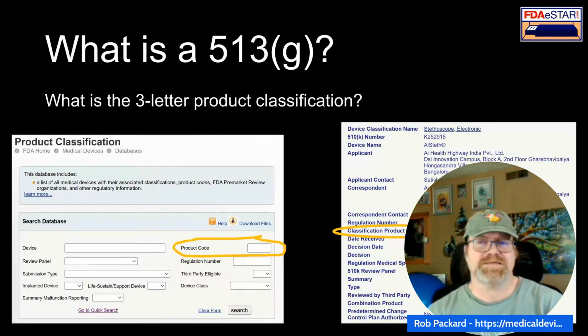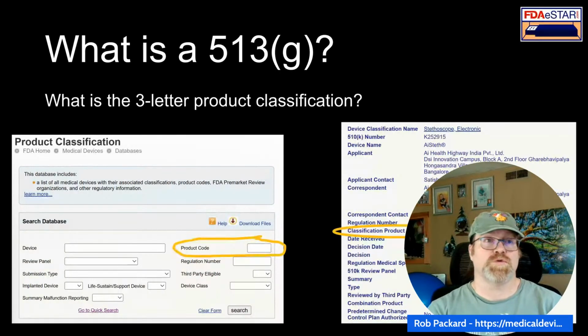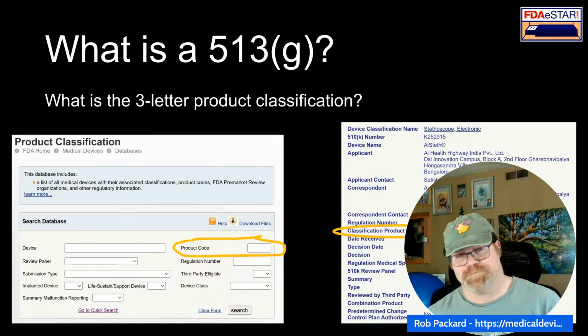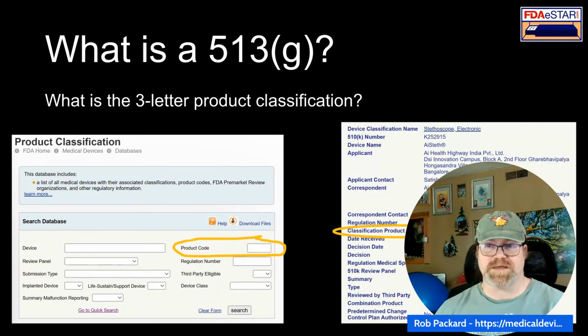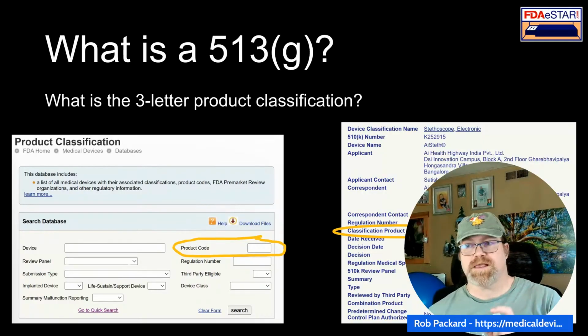Well, if you've added some other functionality to this device, or it's used for a very specific indication that normally biofeedback devices are not used for, then you're in a situation where you need to convince the FDA that you're right and they're wrong. In that particular case, there is a place in the regulations where it's called the limitations of exemption. It's always the first 3 letters of the regulation.